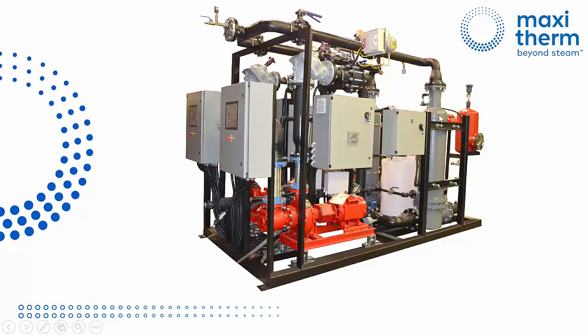It's a redundant system. There are two heat exchangers side by side, vertical flooded heat exchangers, whose principle I will cover in a few slides. Control panel over here, variable speed drive, electric wire. We like to call this package the ultimate five package because there are only five connections for the contractor: one steam inlet for both, one condensate outlet, liquid in and out, and power, ready to start.